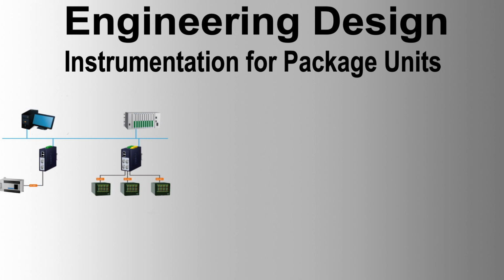5. Equipment layout drawings showing the location of the instruments, junction boxes, local instrument panels, the cable routing between the individual instruments, junction boxes, and panels. 6. If cable junction boxes are included in the supply of the equipment, the documentation shall include terminal arrangement, signal wire allocation, and the make, type, and size of the cable glands. 7. All equipment calculation sheets, e.g. for control valves and flow measuring devices. 8. A list of the trip and alarm settings.